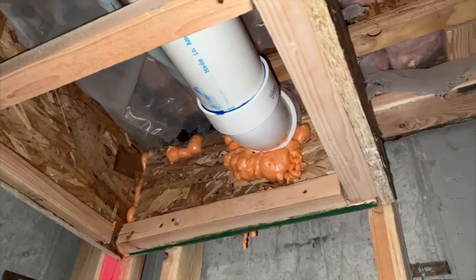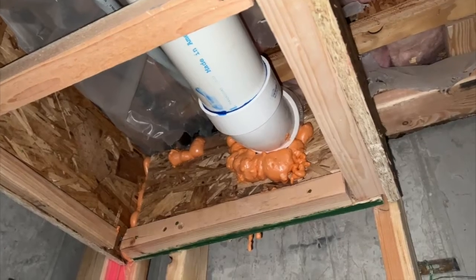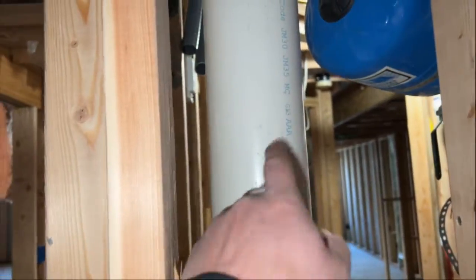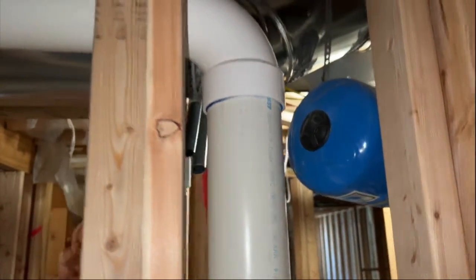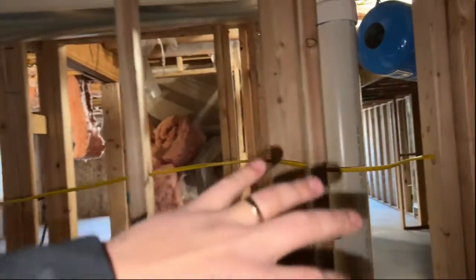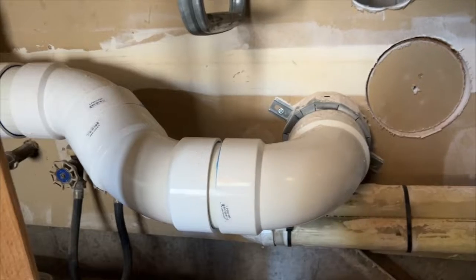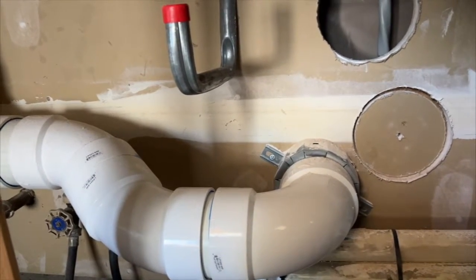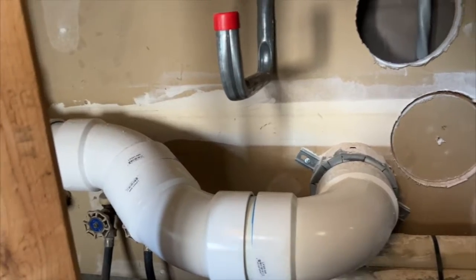One important part of the radon system is the vacuum motor, which we install up in the attic space so that the entire line set has a negative pressure, not a positive one. We want that vacuum sucking the air out, not blowing it out. That's a benefit because if this pipe were ever punctured by a nail — say, someone hanging a picture frame — it would just contribute additional airflow going out of the home, rather than blowing radon gas somewhere else. Here is where the radon system passes to the upstairs, and you can see a metal collar on the pipe to block fire and maintain the fireproofing that the drywall otherwise provides.